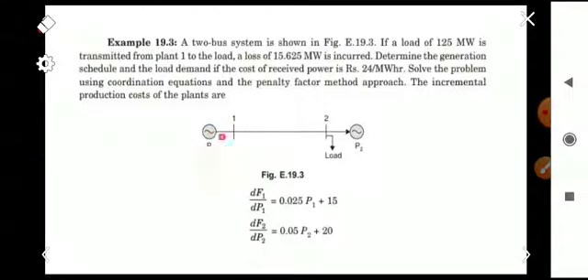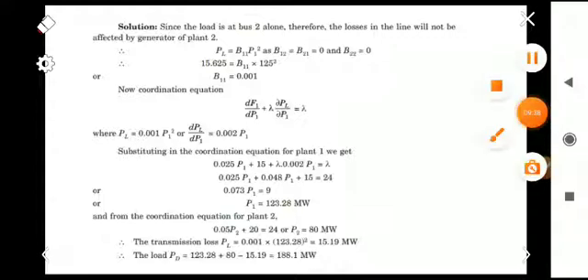The losses are given as 15.625 MW and P1 = 125 MW. Substituting into PL = B11·P1² and solving, we get B11 = 0.001. Now we write the coordination equation: dF1/dP1 + λ·(∂PL/∂P1) = λ.